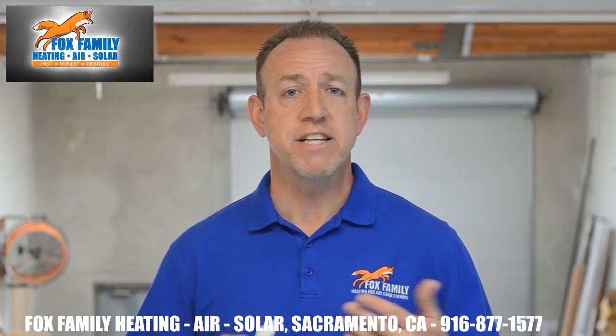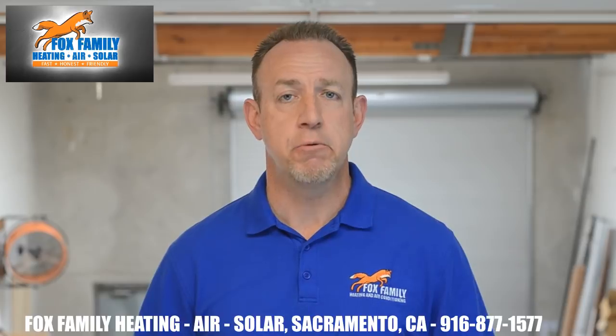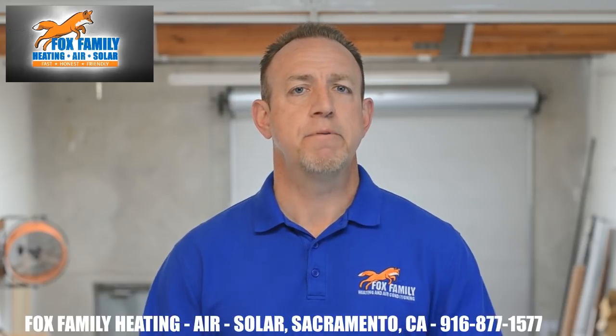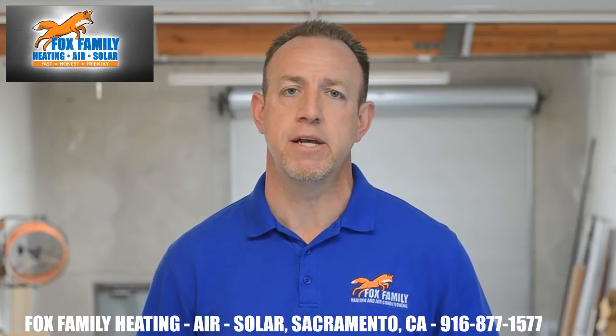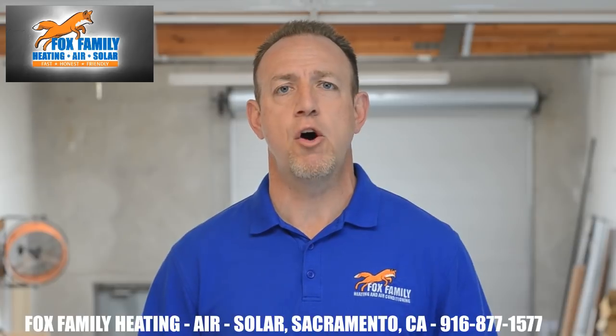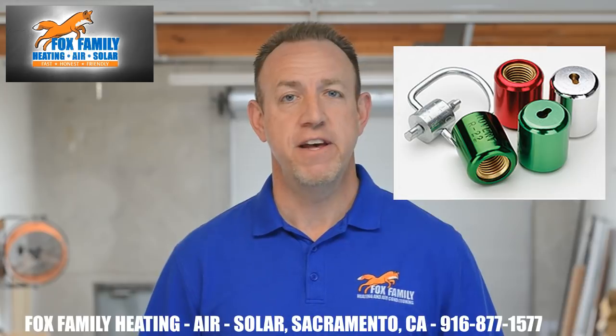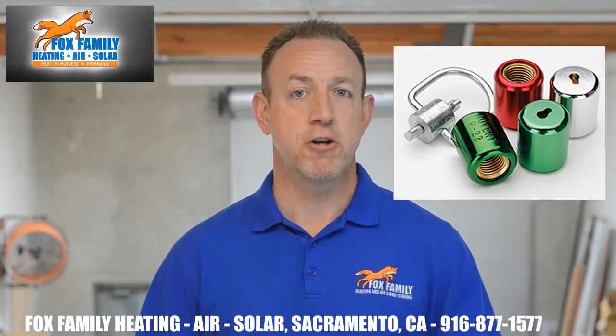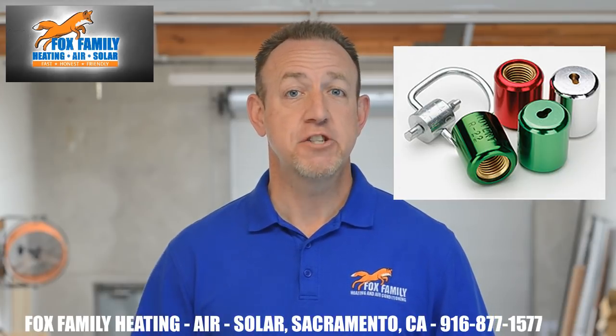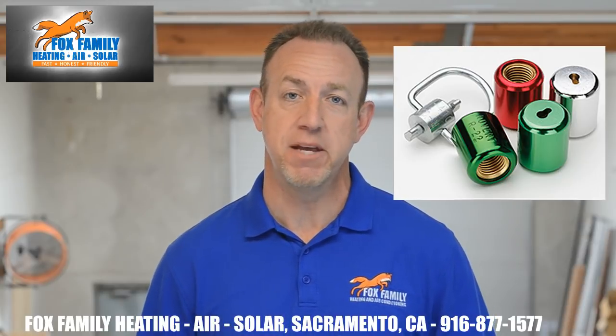This doesn't have to be another great selling opportunity. They're just locking caps, and yes, they cost about $350 for a pack of 50 of them, but this is just another opportunity to protect ourselves from liability. Charging a reasonable price to cover your costs is really all we as HVAC owners should be doing here. At Fox Family, we use no-vent locking caps. They're color-coded green for R-22 and red for R-410A refrigerant, and each color has its own specific key, so I always carry the red and green keys with me in my tool bag.